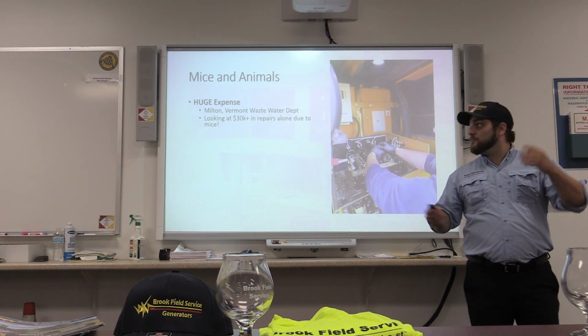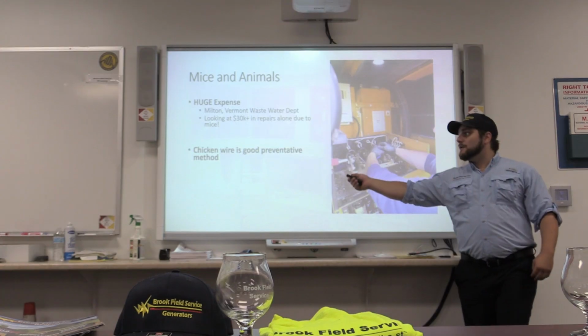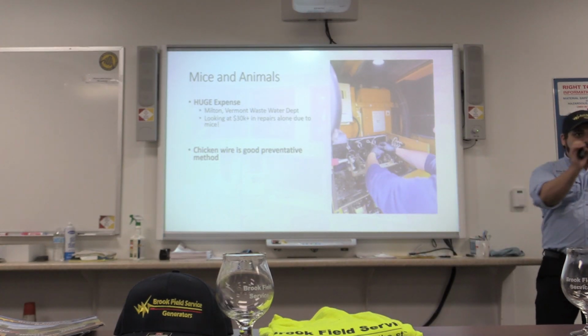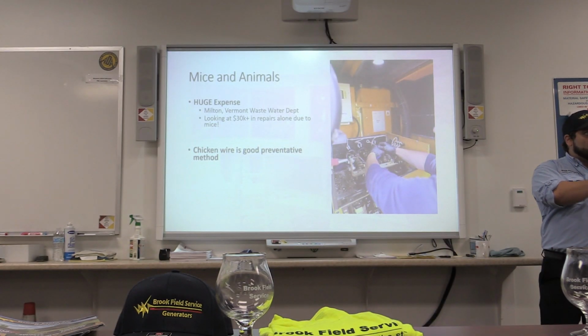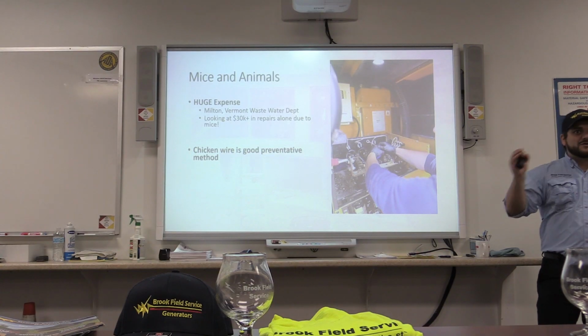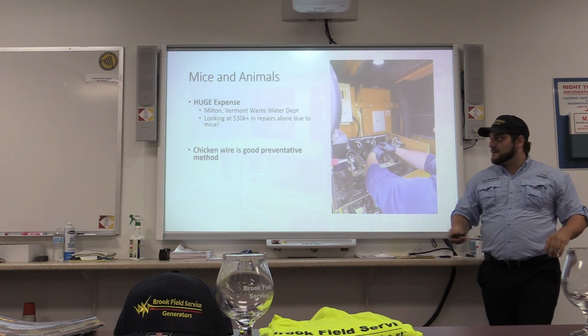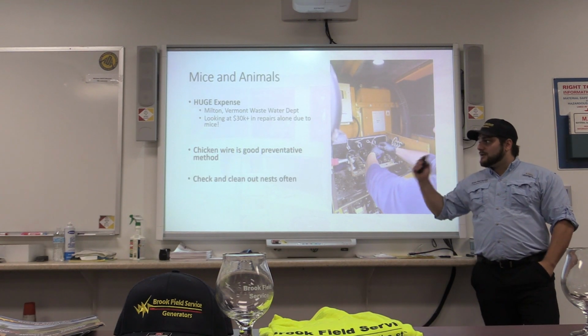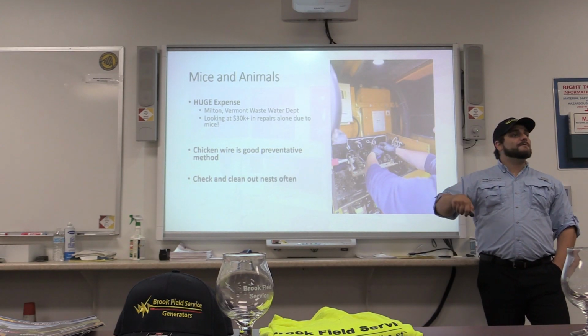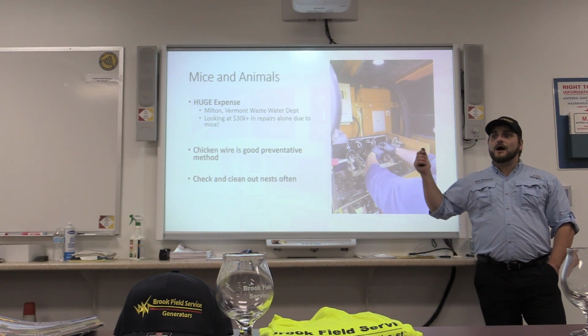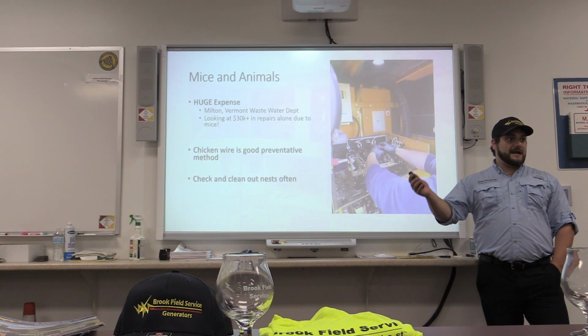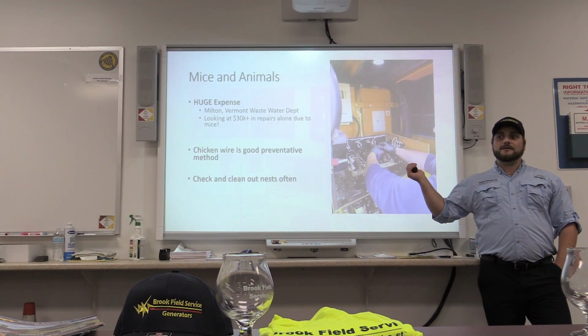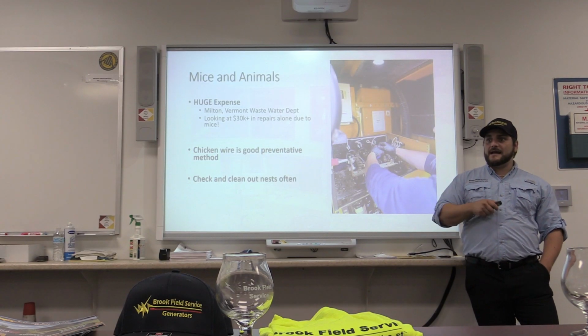So to Josh's point, do whatever you can for abatement. We recommend chicken wire, especially very fine gauge chicken wire with small holes so they can't get through, not the wide stuff for actual chickens. Check and clean out nests often, to the point of making sure you're inspecting your systems weekly, based on NFPA, or monthly at minimum. This should be part of the abatement remediation.